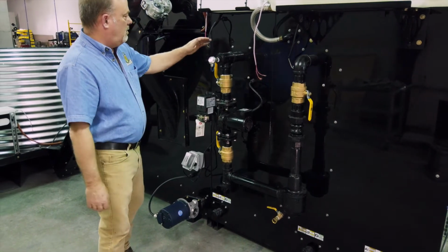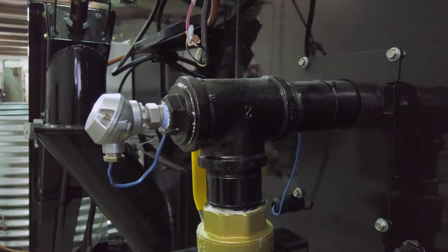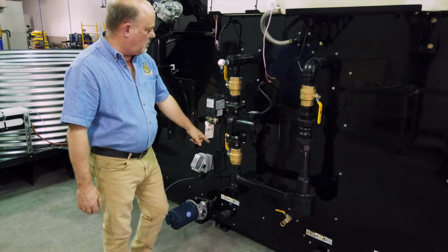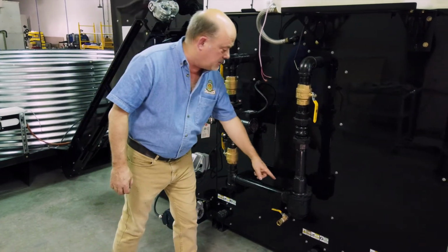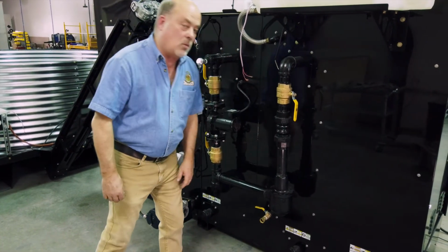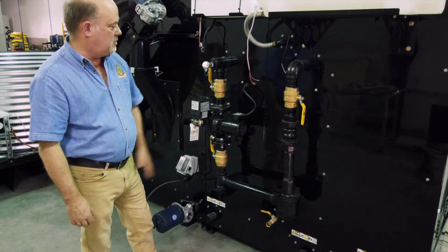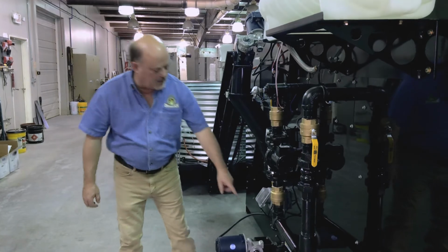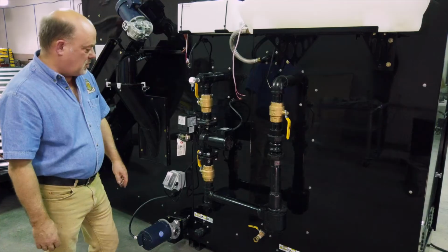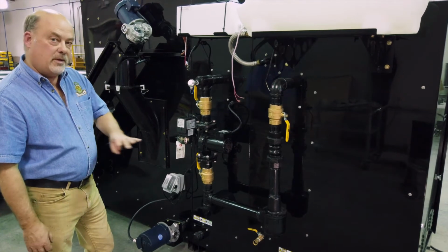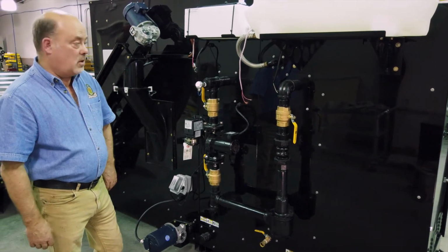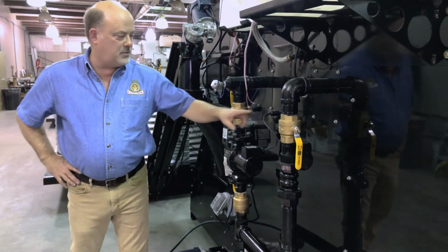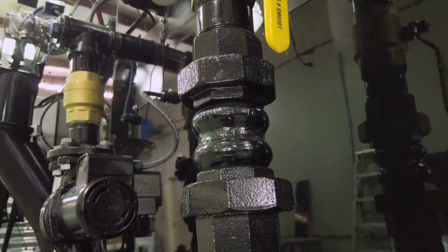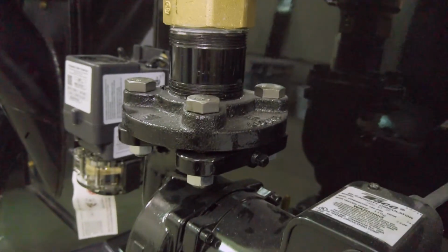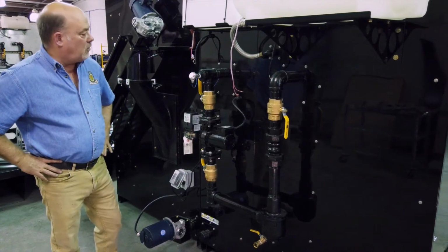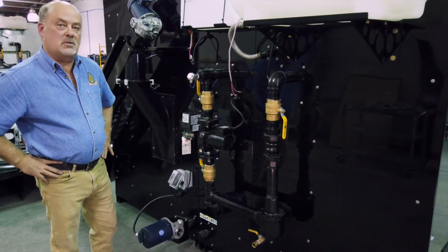Here we measure temperature of the hot water. Probe goes on inside there. Water goes this way. Is not allowed to come back into the system till this protection valve lets the water up to 135. That way we protect the machine from condensing inside. And then down here we have the fill/drain, where you would pump in your glycols in your water. We build in the isolation valves. For maintenance purposes, we have a flex fitting. We have flanges on either side of the pump, so if there is ever an issue with the pump, you can just isolate it out so you don't lose a lot of water. So it's a nice system designed with maintenance in mind.